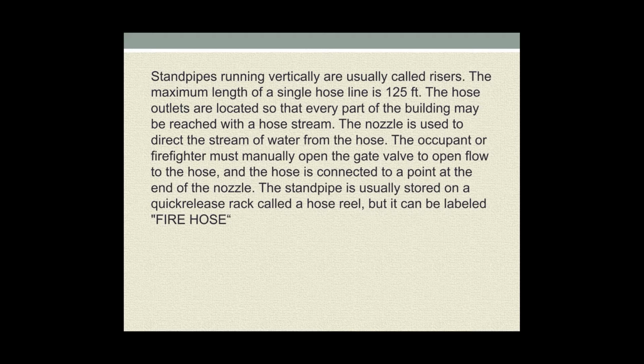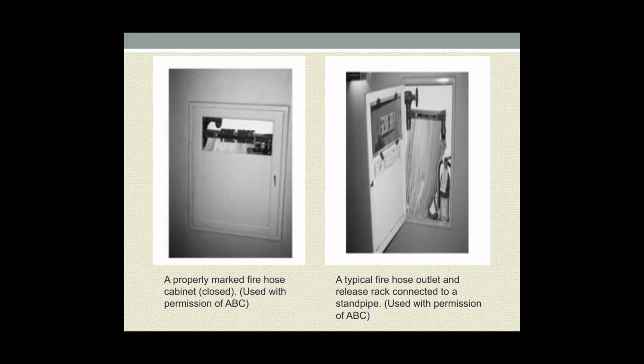Standpipes running vertically are usually called risers. The maximum length of a single hose line is 125 feet. The hose outlets are located so that every part of the building may be reached with the hose streams. The nozzle is used to direct the stream of water from the hose. The occupant or firefighter must manually open the gate valve to open flow to the hose, and the hose is connected to a point at the end of the nozzle. The standpipe hose is usually stored on a quick-release rack called a hose reel, but it can be labeled fire hose.